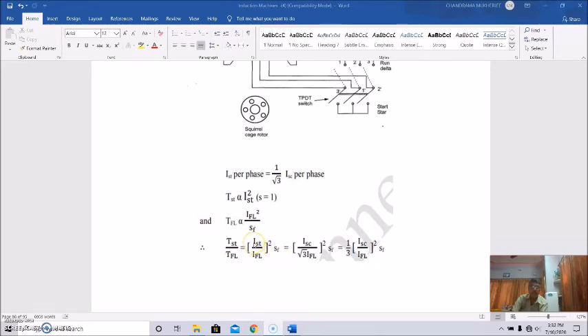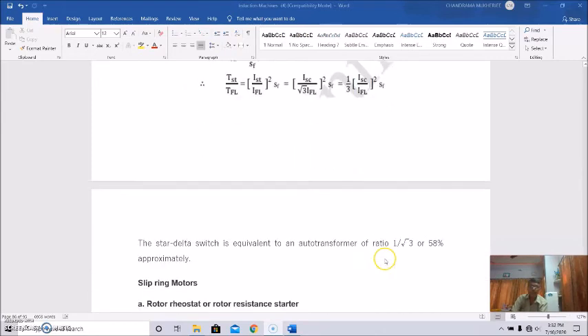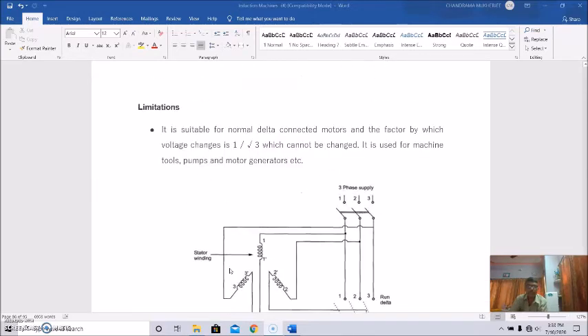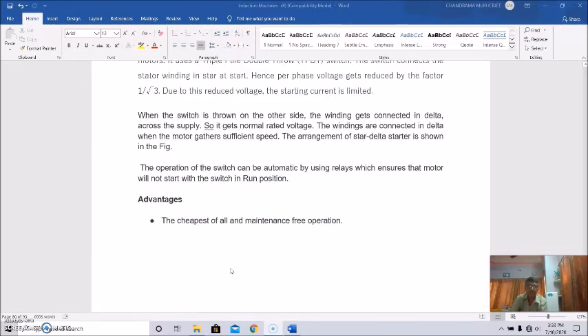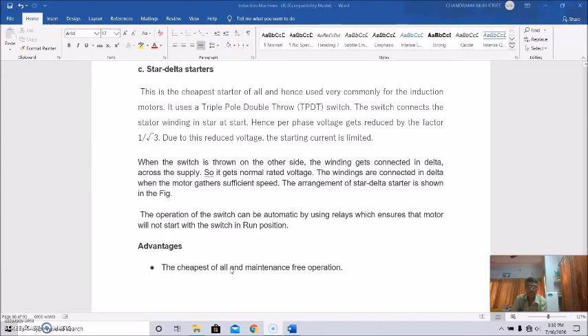But this I_ST is equal to 1 by root 3 times this. So you can write I_SC by root 3 I_FL whole square into S_F, that is equal to 1/3 I_SC square by I_FL square into S_F. So we say the star delta switch is equivalent to an auto transformer of ratio 1 by root 3, or 58% approximately. So that's all about this star delta starter.